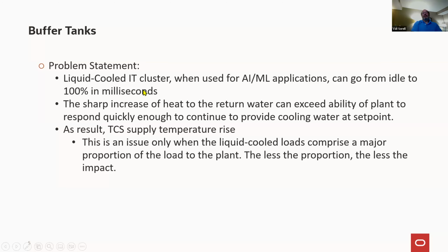So these IT clusters that are now used for high performance computing, AI, machine learning, at first it was reported that they can go from 0 to 100 in milliseconds. And it's actually not true. It's not 0. It's actually an idle state, which can be 20, 30, 40% of the maximum condition. But when a workload is sent to a processor, it theoretically just goes all out, goes to 100%, and it does do that in milliseconds.